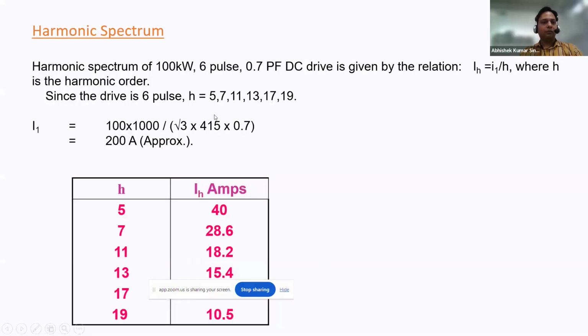Yeah. So now we will talk about the harmonic spectrum. As I discussed in the previous slide about the magnitude, we will understand here what that term means. Suppose we have a 100 kilowatt 6 pulse 0.7 power factor DC drive, and we will find its current. This is basically P is equal to root 3 VI cos phi. That is the simple formula we use. So basically the current is 200 ampere.